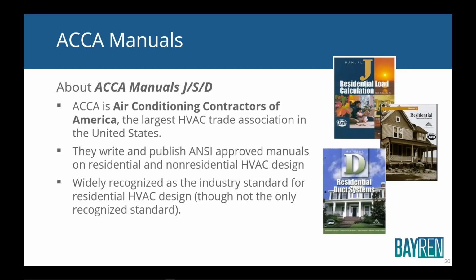So you hear us talking about ACCA Manual JS&D. What is ACCA? What is Manual JS&D? Well, ACCA is Air Conditioning Contractors of America. It's the largest HVAC trade association in the United States. They write and publish ANSI approved manuals on residential and non-residential HVAC design. And they're pretty much recognized as the industry standard for HVAC design. Most of the codes will say, do your loads based on ACCA Manual JS&D or equal. Manual JS&D are actually based on ASHRAE calculations. They've just been customized and tabulated to make them easier to use, but they are essentially based on ASHRAE formulas and math and things like that, okay?